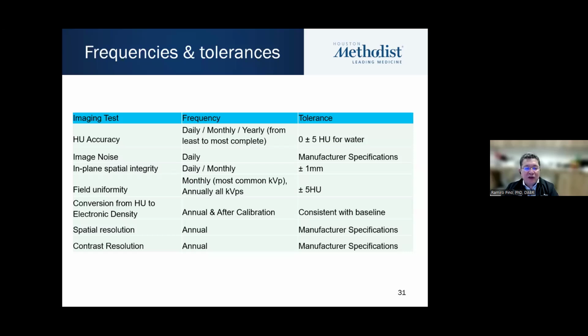In-plane spatial integrity, it's important that you don't have distortions in the image acquired. Field uniformity is typically acquired monthly and annually, and the conversion table should be checked annually and after every calibration, as well as the spatial resolution and contrast resolution. Although, since you do multiple Hounsfield unit plug checks monthly, it's pretty straightforward to check spatial resolution and contrast resolution monthly as well.